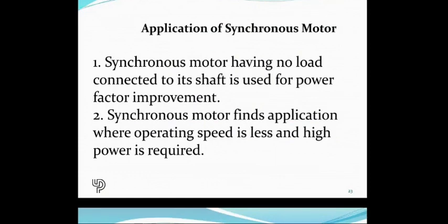One special advantage or special application of a synchronous motor is that if the load power factor is bad, a synchronous motor can help in improving the power factor. This is one very standard technique in industry for improving power factors. Of course, the motor has to be connected to no load.